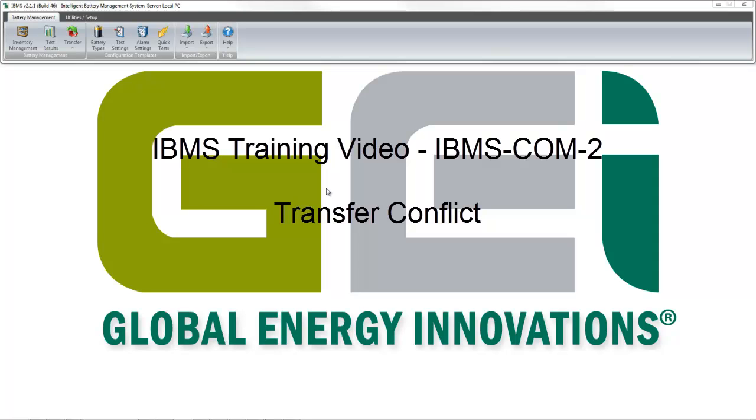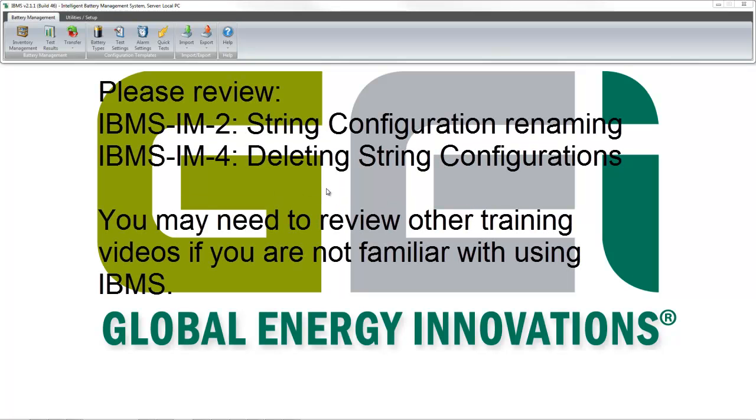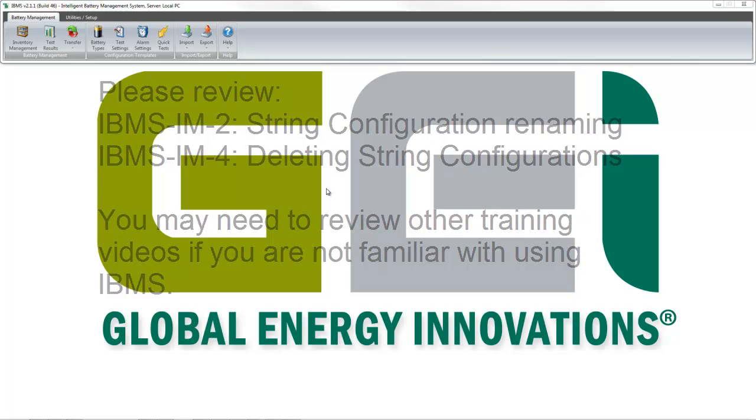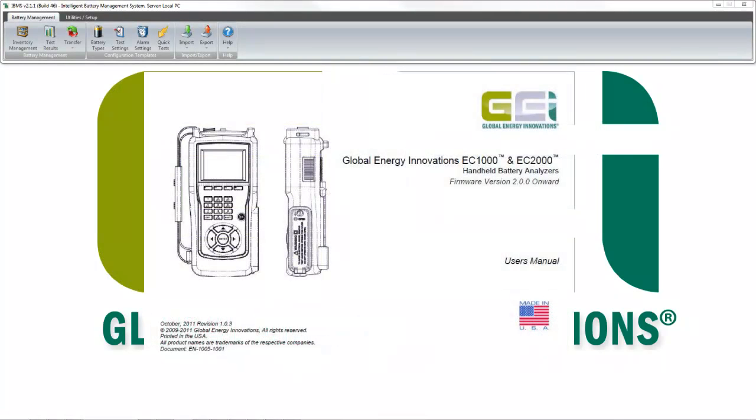This training video deals with transfer conflicts and how to handle them. You may want to review the training video IBMS-IM-2 for renaming string and IBMS-IM-4 for deleting string. You can also consult the EC Series Analyzer user manual if you need to perform these functions in your analyzer. Please note that you cannot rename a string configuration in the analyzer once a test was initiated for the string.